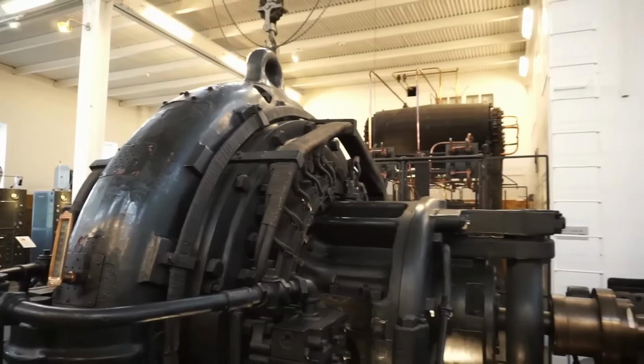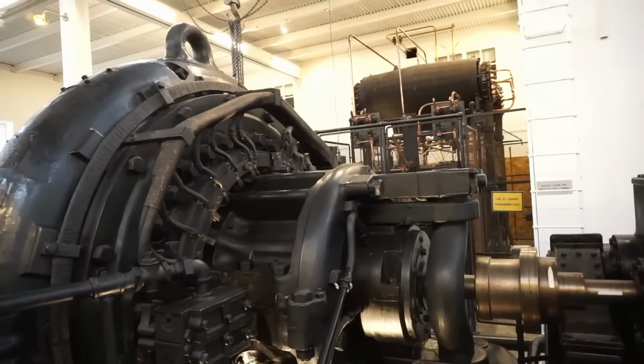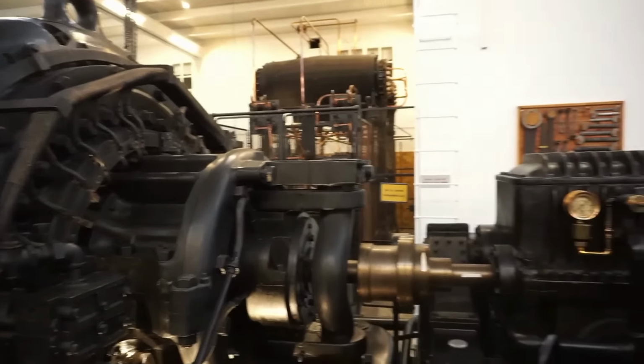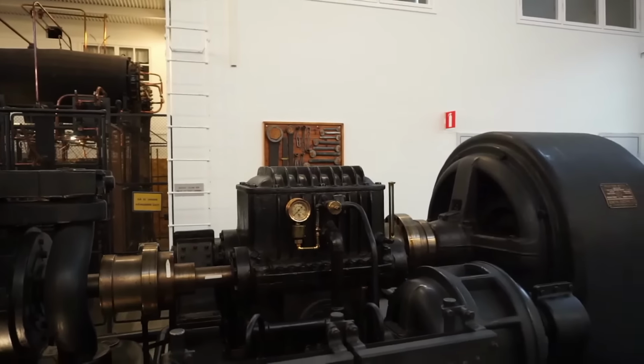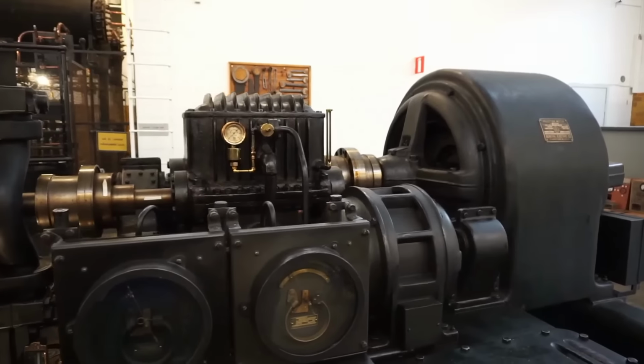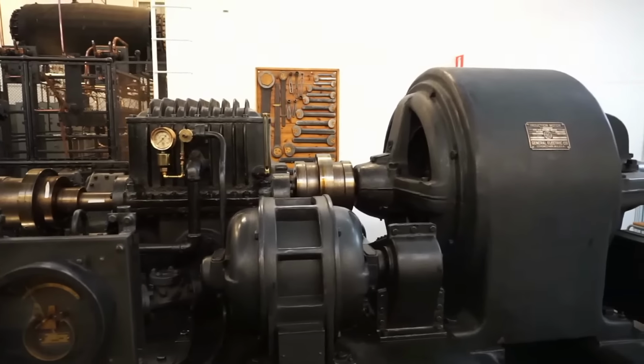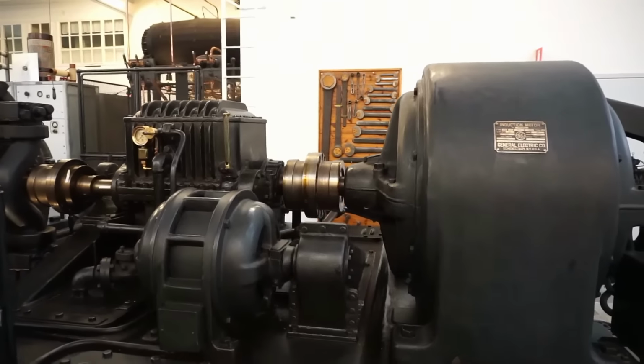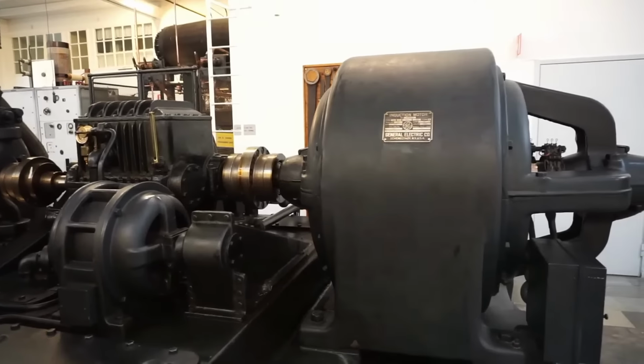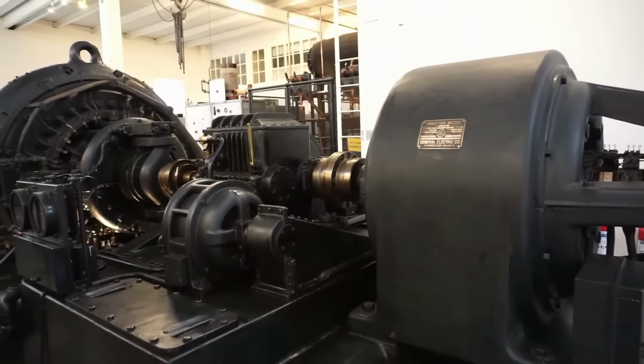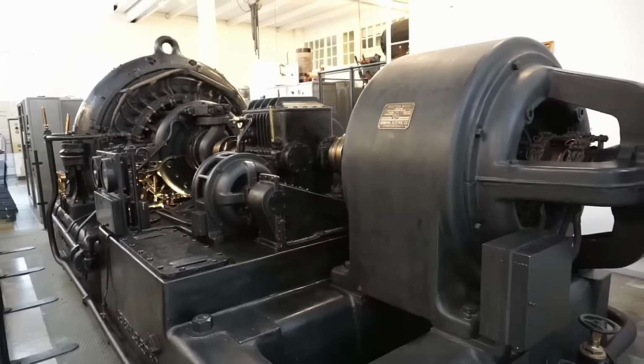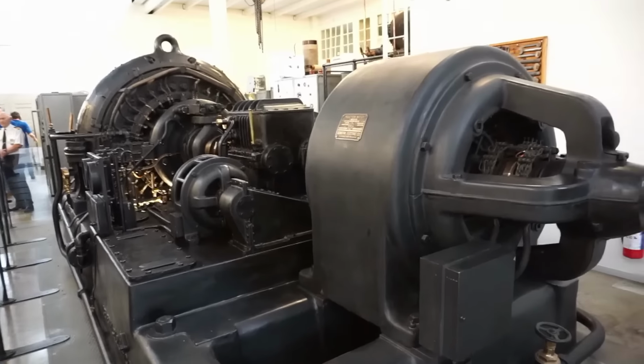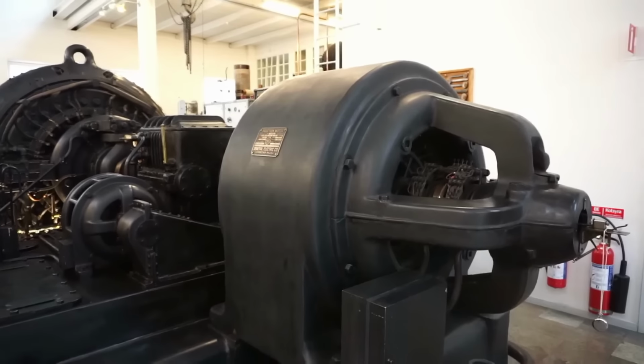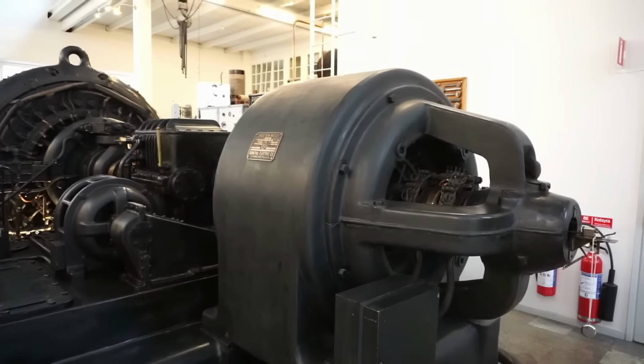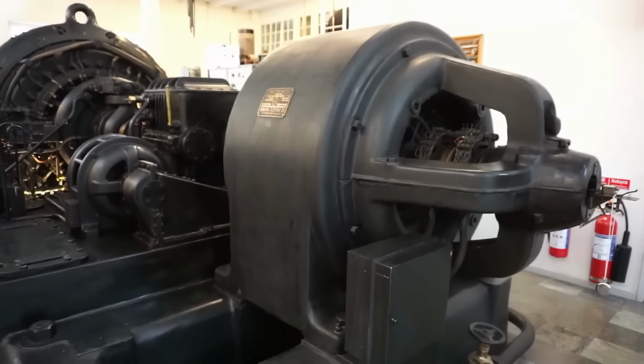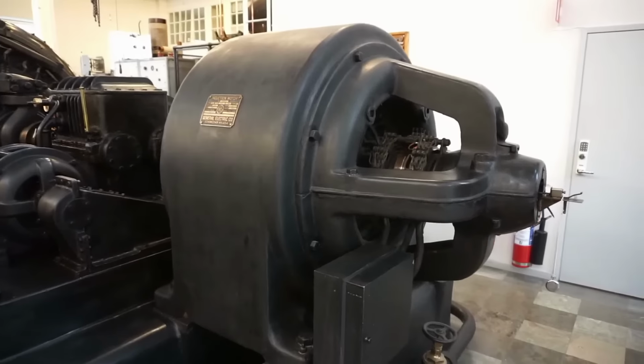The disc is driven by the main motor over here via a gearbox that is shifting up the speed almost three times. So the frequency of the motor is directly related to the frequency. So it is of great importance to keep the motor speed constant and correct. The main motor is a 500 horsepower asynchronous motor that is driven by 2,300 volt two-phase winded voltage. The stator is two-phase winded and the rotor is three-phase winded.